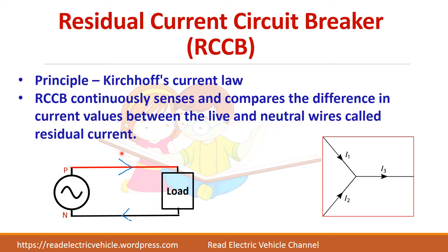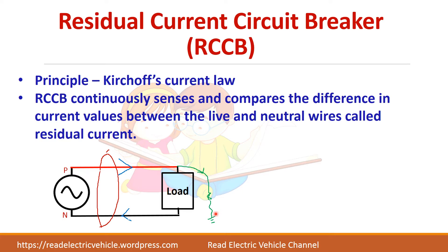The RCCB senses the difference between the two currents. Under normal conditions, these two currents should be equal. But whenever there is a fault, a part of the current will flow away. Due to that, the current flowing through the phase line will not be equal to the current flowing through the neutral line. There will be a difference of current, which is called the residual current. The RCCB will sense this residual current and trip the breaker, opening the circuit.